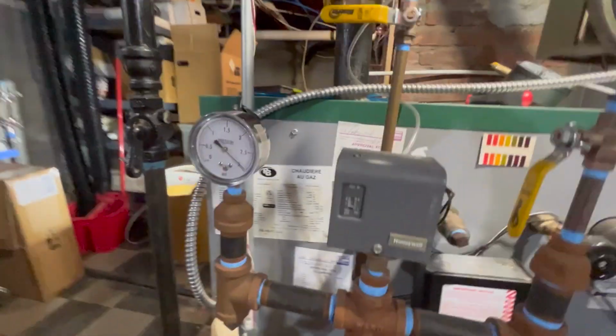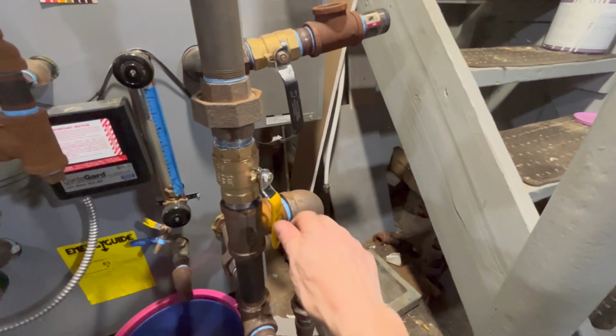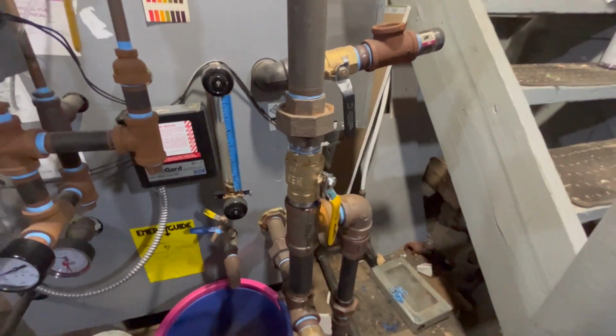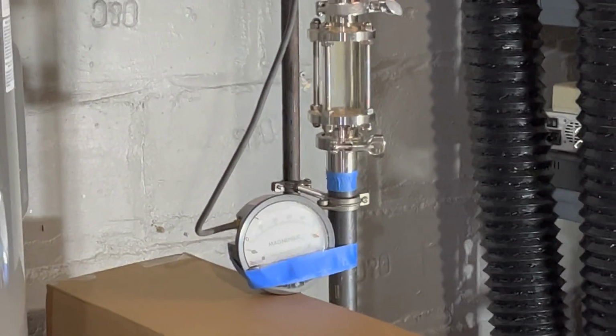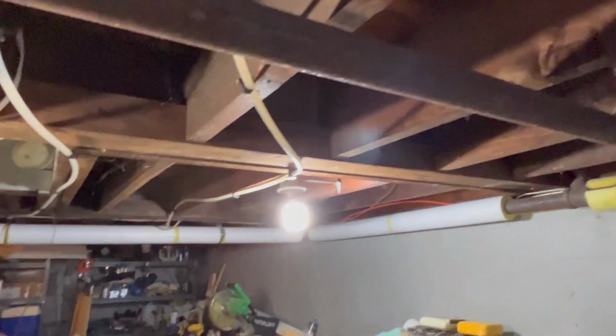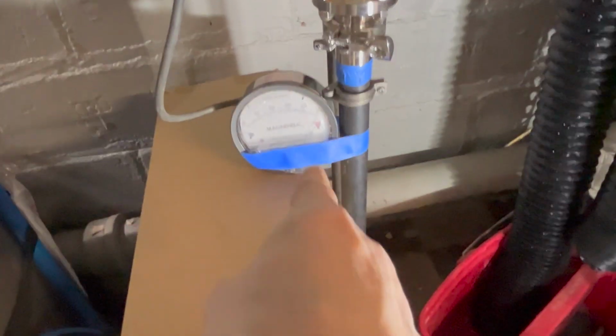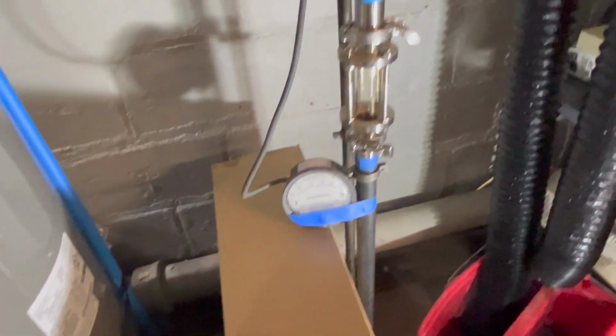2.5, 2.5. Now we're up to 3. Well, what keeps that water from rising over there then? It's not the equalizer, we know this. It's the main. The main has a little bit less than 3. Very little bit less than 3, we know, because we saw the Magnehelic was matching the other meter.